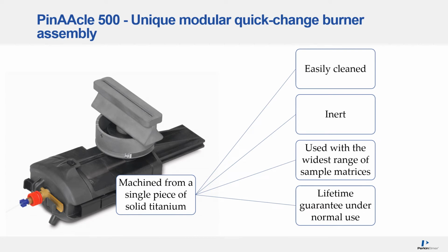All PinAAcle flame AA instruments include a pre-mix burner system. This high-strength, inert plastic burner chamber is angled for proper drainage and includes an adjustable nebulizer, either a high sensitivity nebulizer as depicted in this picture, or a stainless steel nebulizer. We would also include with these systems a standard titanium 10 centimeter single slot burner head for air acetylene operation. Now these burner heads are easily cleaned. They are inert because they are made of solid titanium block, and they are available to be used with a wide range of sample matrices, and they all come with a lifetime guarantee under normal use.